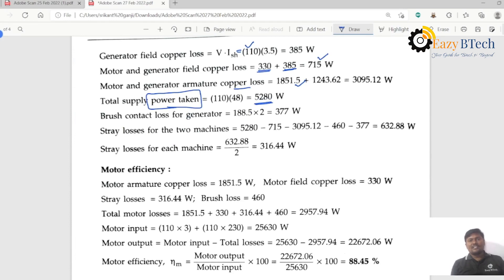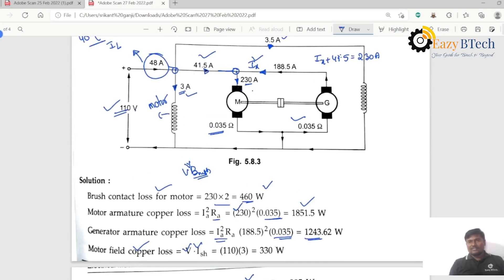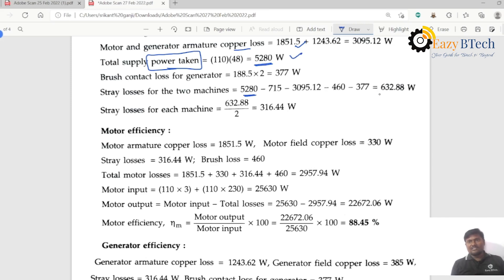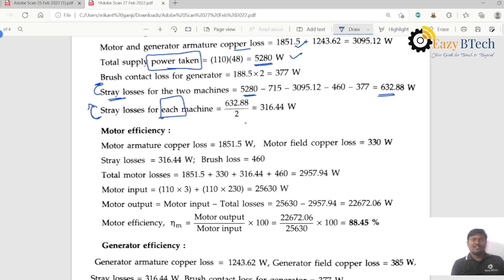The brush contact loss for the generator: two brushes at one volt per brush, with 188.5 amperes, equals 377 watts. From the input power supply, subtracting all losses gives stray losses for both machines of 632.88 watts. Stray losses for each machine is 632.88 divided by 2 equals 316.44 watts.